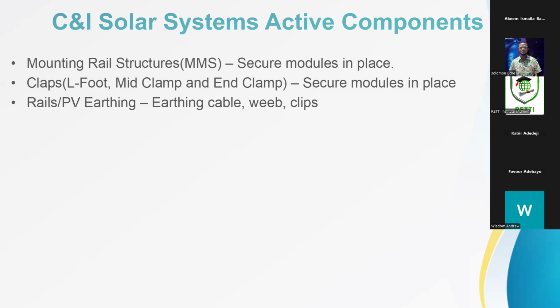So we have the rail clamps, the PV cable, the Weeb, and the clips. On this part, we've had experience where the panel sits on the rail. If I do the earthing for all the rails and link the rails together, automatically my PV array is on top of the rail, so it means my array is connected to the rail, and the earthing too.